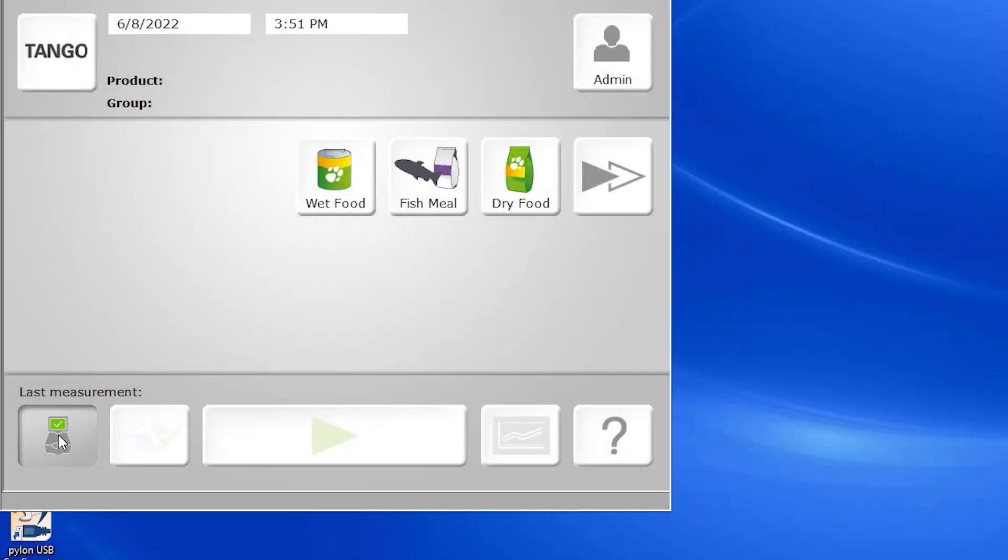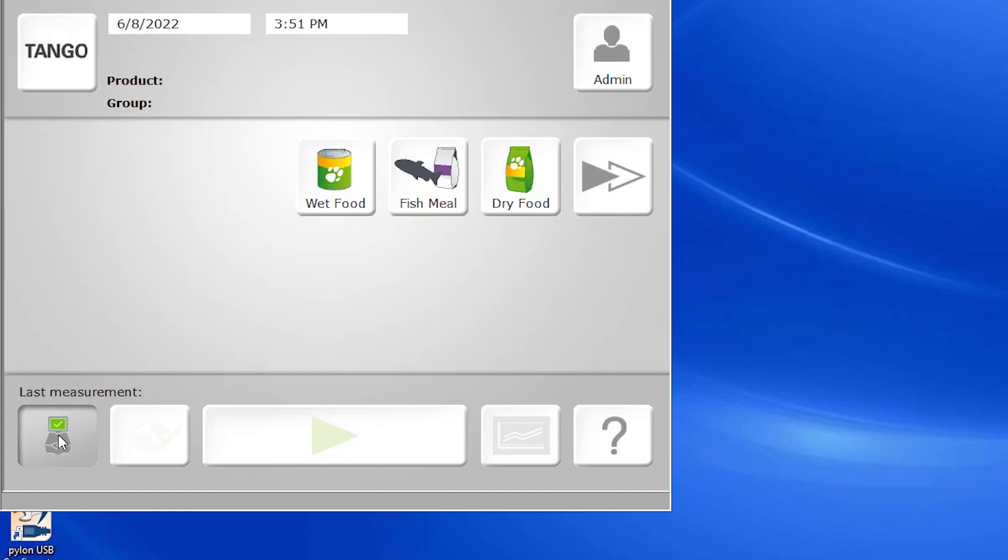When the icon is green, it's indicating that the status of the spectrometer is okay and it's ready for measurement. Similar to the LED lights on the front of the instrument, a yellow colored screen on this icon indicates a warning for either hardware components or a diagnostic test that needs to be run, while red on the other hand indicates an error, which signifies that sample measurement will not be possible.